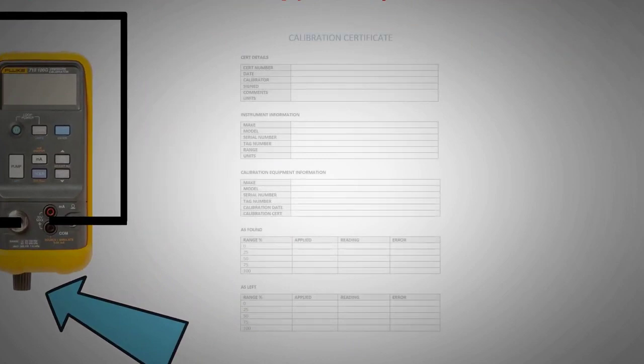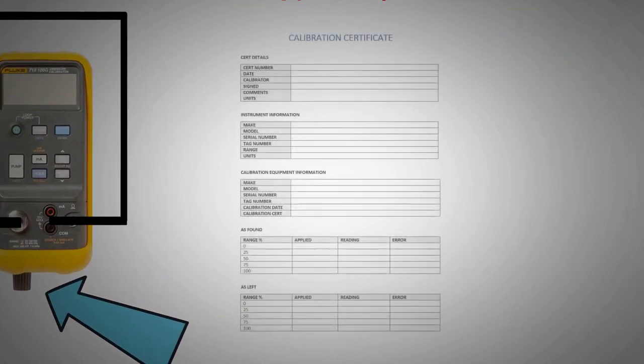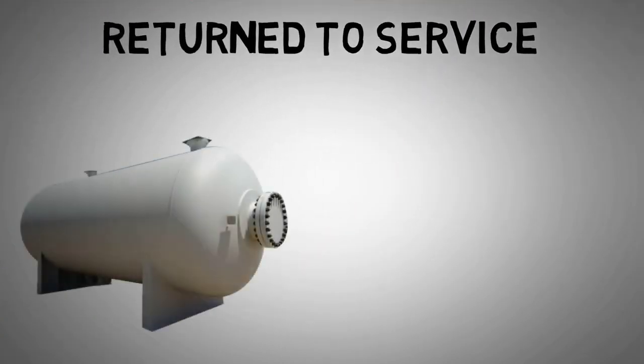The information we have obtained about the accuracy of the transmitter will be used to create a calibration certificate, usually electronically. This will then likely be stored in the maintenance management system for future reference. The equipment is usually labelled as calibrated and dated and then returned to service.